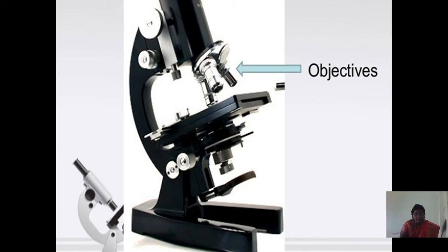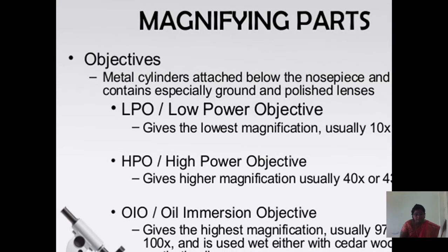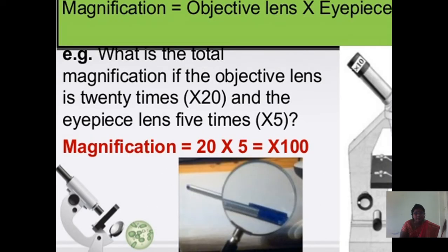Magnifying parts include the objectives, which are metal cylinders attached below the nosepiece containing specially ground and polished lenses. The low power objective gives lower magnification, usually 10 to 30x. The high power objective gives higher magnification of 40 to 43x. The oil immersion objective gives the highest magnification, usually 97 to 100x, and is used wet with either cedar oil or immersion oil. The total magnification is calculated as objective lens multiplied by the eyepiece. For example, if the objective lens is 20x and eyepiece is 5x, the total magnification is 20 × 5 = 100.